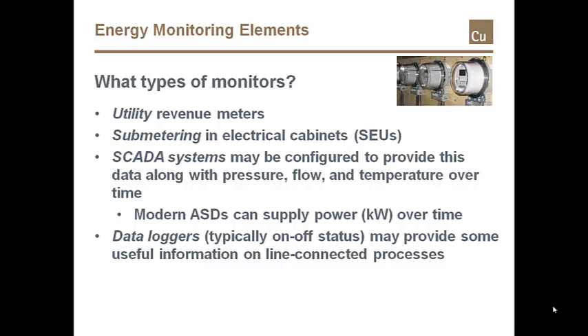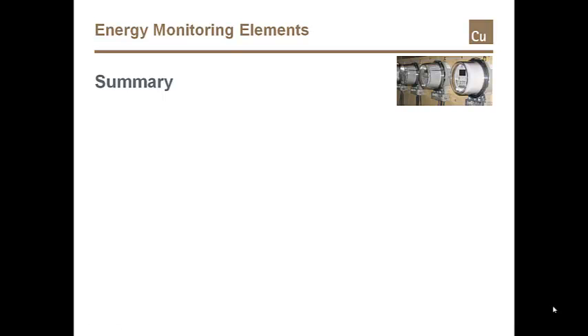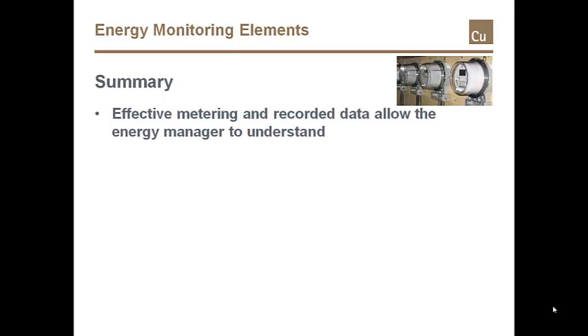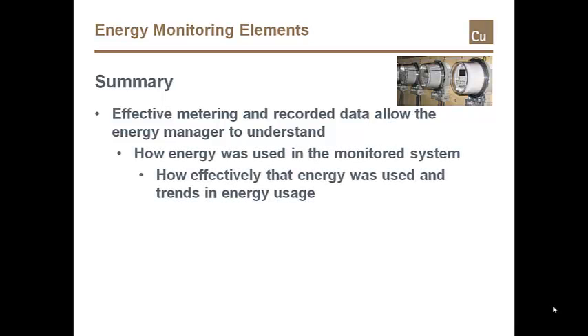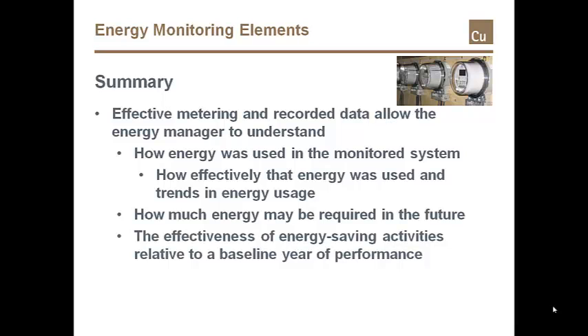Process data labels usually indicate rated voltage and current. This information, along with the hours of operation as indicated by the data loggers, may be used to estimate energy consumption. In summary, effective metering and recorded data allow the energy manager to understand how energy was used in the monitored system, how effectively that energy was used and trends in energy usage over time, and the effectiveness of energy-saving activities relative to a baseline year of performance.